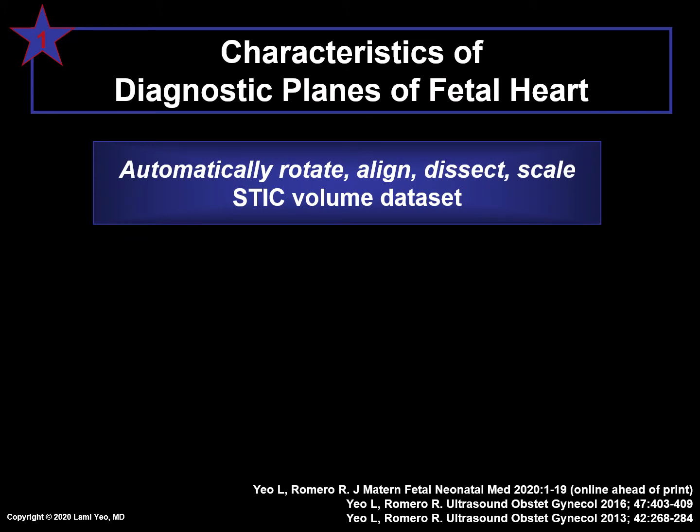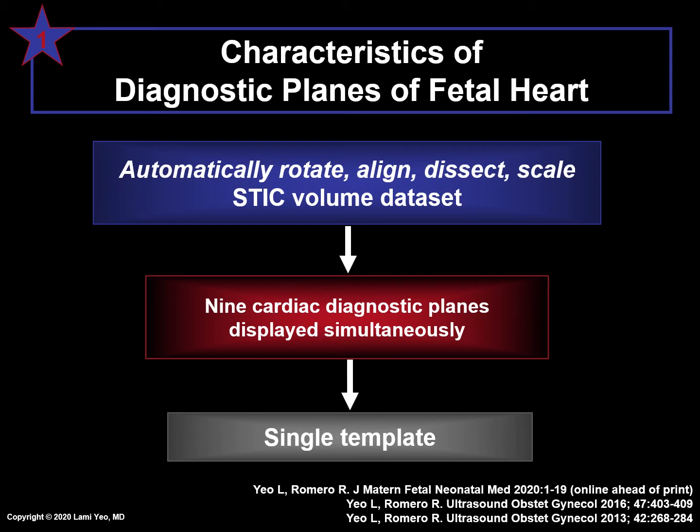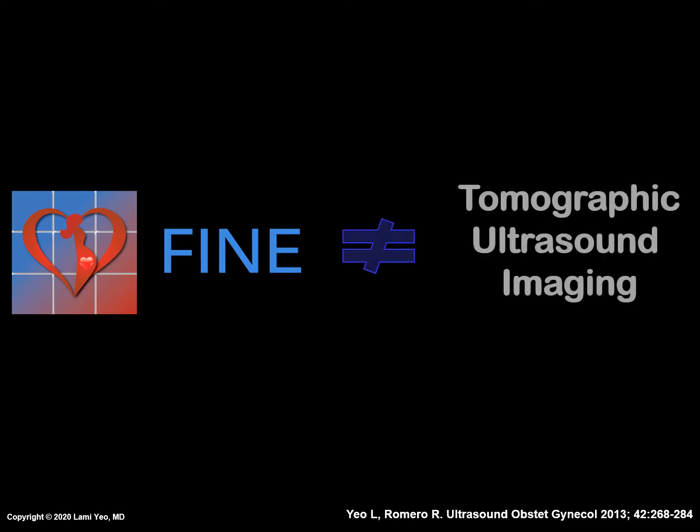FINE will automatically and immediately rotate, align, dissect, and scale the STIC volume dataset to display 9 cardiac diagnostic planes simultaneously in a single template. It is important to point out that both transverse and sagittal images are shown at the same time. Therefore, FINE is not equivalent to what is known as tomographic ultrasound imaging or multi-slice imaging. They are completely different from each other.